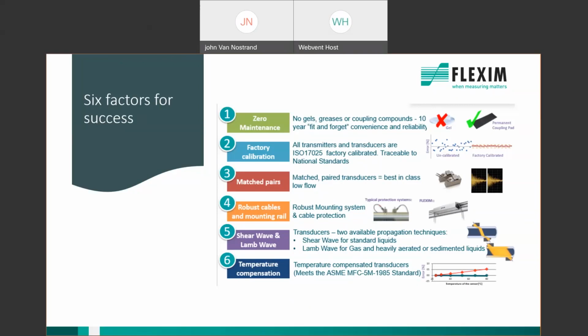Another thing that we do is we match those transducers, the crystals. We like to call that a wedding. We have a lot of weddings at FLEXIM. That just means that we're matching the upstream and downstream crystals inside the transducers to ensure the tightest accuracy possible. We integrate the cables in the mounting so that there's a robust mounting solution, and they're industrially hardened, and there's no worry about how to connect the transducer cables, whether it be upstream, downstream, and so on.